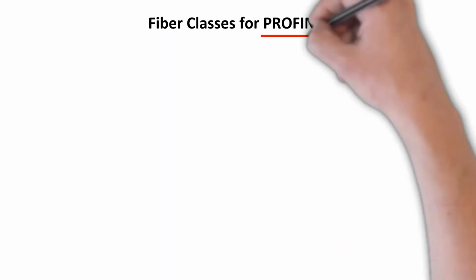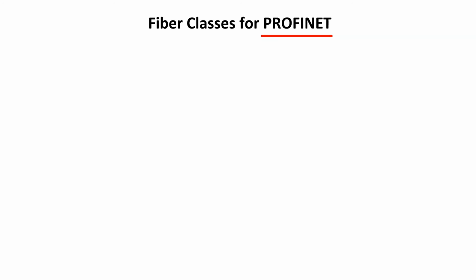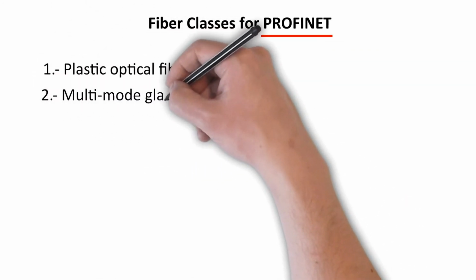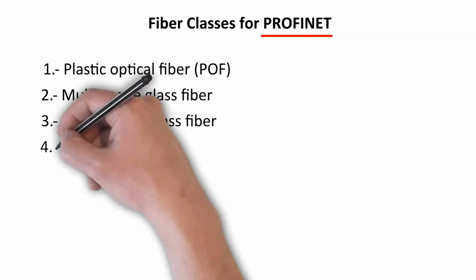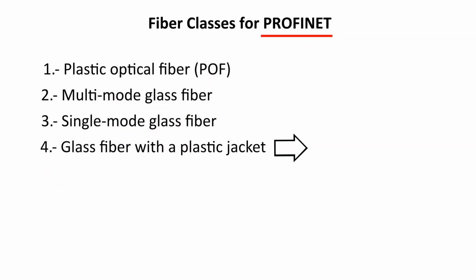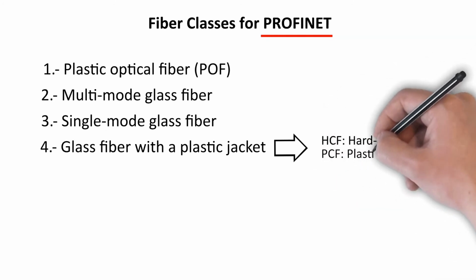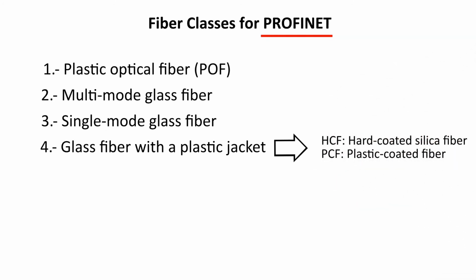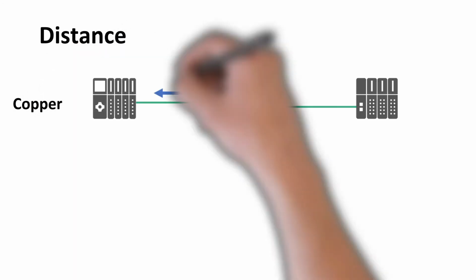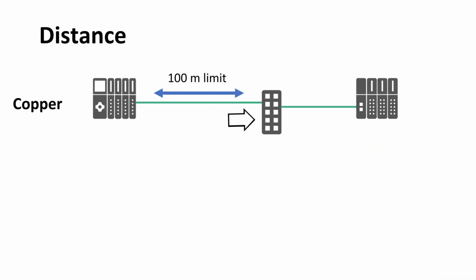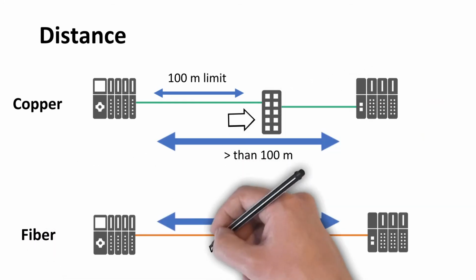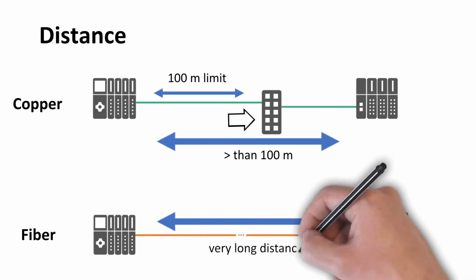4 different fiber classes can be employed when using optical fibers for Profinet. Those 4 classes are POF, multi-mode glass fiber, single-mode glass fiber, and glass fiber with a plastic jacket, HCF or PCF. Now, let's cover important considerations when installing fiber and copper cables. Distance. Individual copper segments are limited to 100 meters before the signal must be refreshed, for example with a switch. Fiber optic cables cover longer distances by default. Some run for over 100 kilometers long.